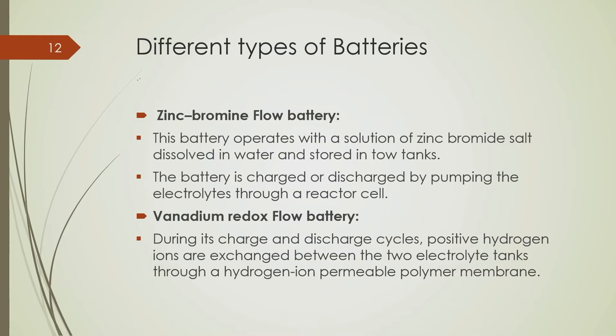Flow battery technology uses a liquid electrolyte flowing through a microporous membrane to generate electrical charge, similar to a fuel cell. This form of battery can store and release energy through reversible electrochemical reactions, and the advantage is the ability to scale the system independently in terms of power and energy. More cell stacks increase the power rating, while greater volume of electrolyte provides more run time. There are different types of flow batteries including zinc bromine and vanadium redox flow batteries.